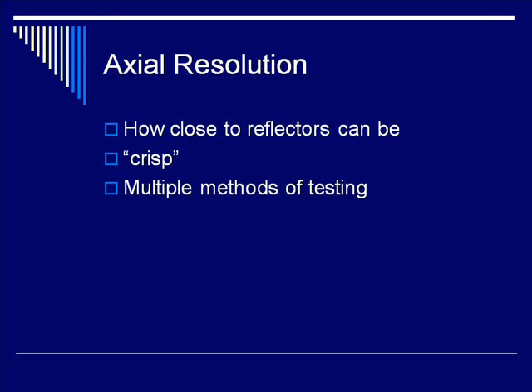Let's discuss resolution. Resolution is generally a measure of how close two reflectors can be and still be resolved. The three kinds of resolution we'll discuss today are axial, which is how close reflectors can be and still be resolved in the near-field to far-field axis; lateral, which is how close reflectors can be in the leading edge to receding edge axis; and elevational resolution, which is how thick the slice of image is that you're looking through at a given moment in time.